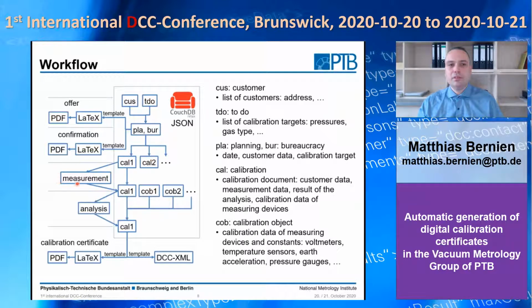Then the measurement receives the values from the calibration document, for example the pressure points at which calibration should be carried out. Then the values are measured and written into the section for the measurement. Measurement programs are written with LabVIEW and Node.js at the moment, and also Clojure. Then in the next step, the analysis program reads the data from the measurement and writes back its results to the analysis sections. Analysis programs are done with R and Python in our case.